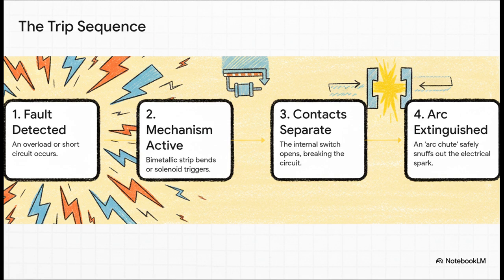When you break a live circuit, you create a really dangerous electrical spark called an arc. Well, inside the MCB is something called an arc chute. It's a stack of metal plates that literally slices that arc into smaller, weaker pieces and snuffs it out safely. So it's not just about cutting the power, it's about doing it without causing another disaster.